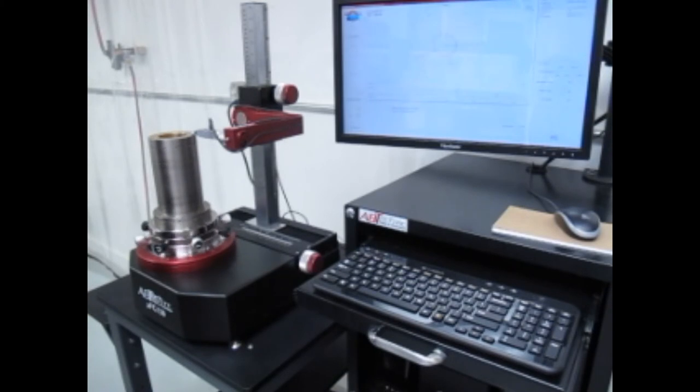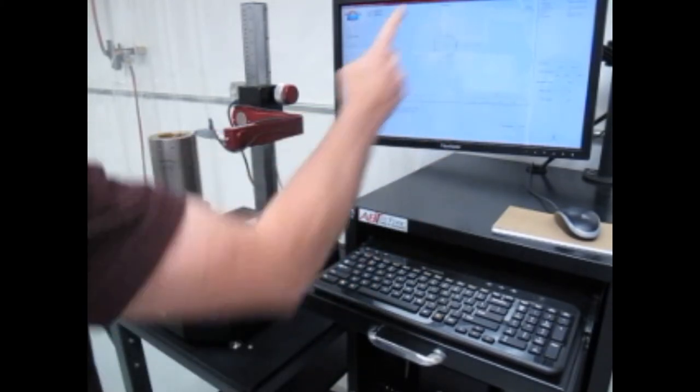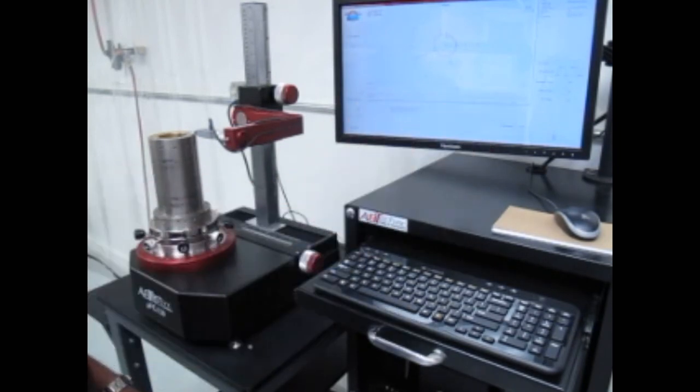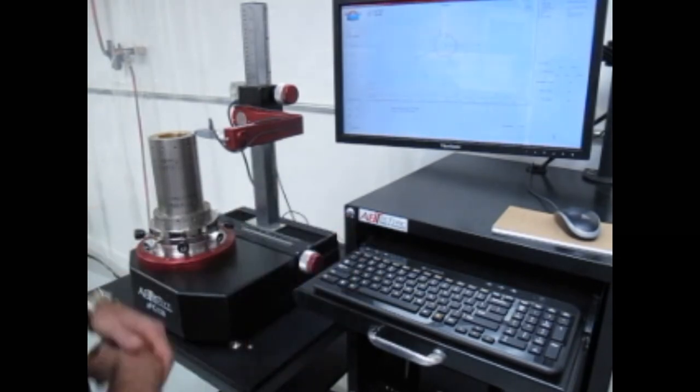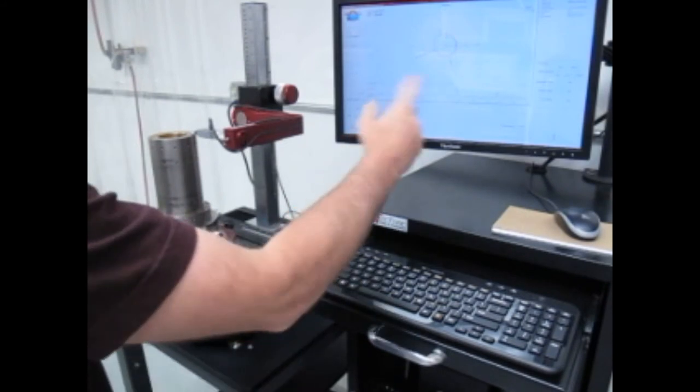Under 12 seconds you'll get a measurement, and it has a polar plot, and I've turned on the optional strip chart here as well, so you can see what that looks like laid out flat. And you can see that I have flatness here of 99 millionths with a resolution of tenths of a millionths.